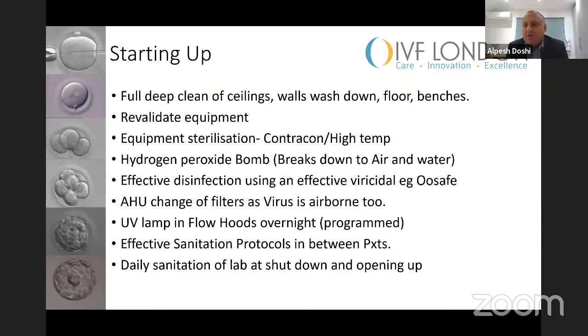Sterilization is very important. Big box incubators have high temperature sterilization systems up to 90 degrees. In some countries you may have a hydrogen peroxide bomb available. In the UK, specialized companies come the night before to set this up in the lab. You keep all equipment doors open, including incubators. You can't be in the lab when it's released because it's toxic, but once released, everything is disinfected and there's no concern about toxicity because it breaks down into air and water.